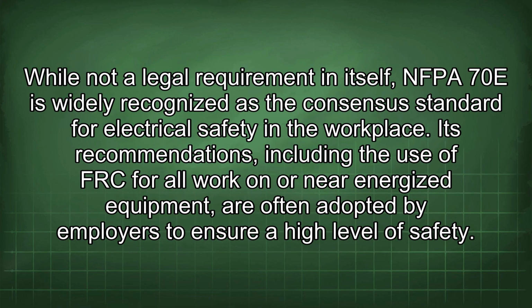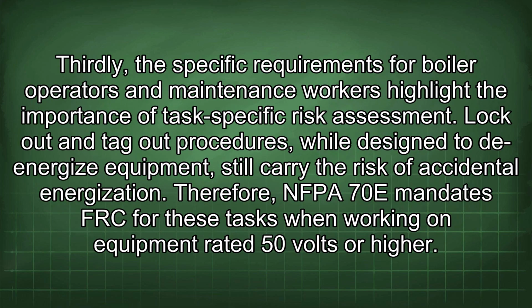While not a legal requirement in itself, NFPA 70E is widely recognized as the consensus standard for electrical safety in the workplace. Its recommendations, including the use of FRC for all work on or near energized equipment, are often adopted by employers to ensure a high level of safety. Thirdly, the specific requirements for boiler operators and maintenance workers highlight the importance of task-specific risk assessment. Lockout and tag-out procedures, while designed to de-energize equipment, still carry the risk of accidental energization. Therefore, NFPA 70E mandates FRC for these tasks when working on equipment rated 50 volts or higher.